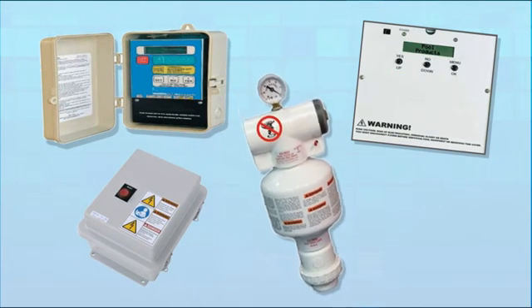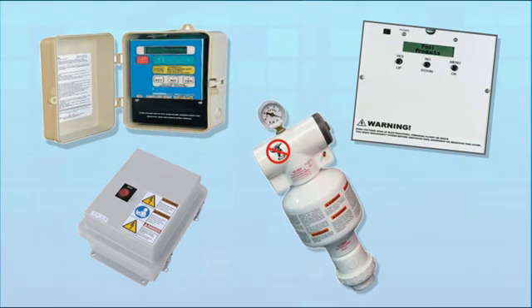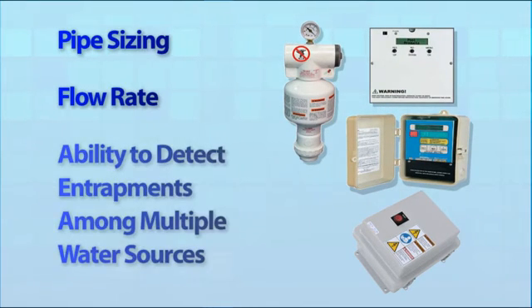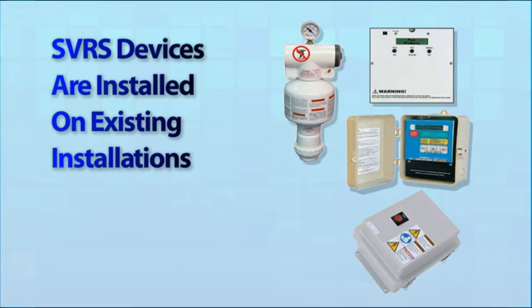SVRS devices should be installed within the scope of the manufacturer's instructions. Pay particular attention to notes about pipe sizing, flow rate, and ability to detect entrapments in the presence of multiple sources of water. SVRS devices have an advantage of being installed on existing installations, avoiding significant renovation and construction costs.